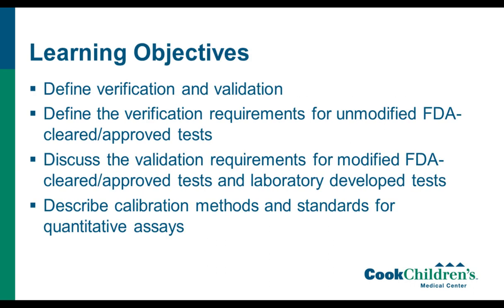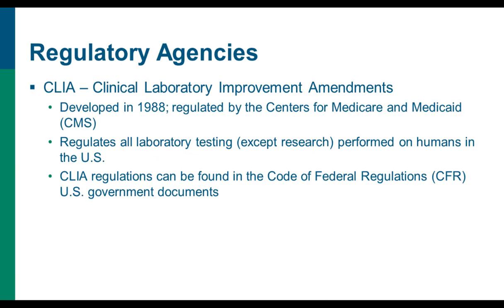The learning objectives for today are first to define verification and validation, and then to define the verification requirements for unmodified FDA-cleared or FDA-approved tests. We'll follow that with a discussion of the validation requirements for modified FDA-cleared tests and laboratory-developed tests, and then talk about the calibration methods and standards that are required for quantitative assays.